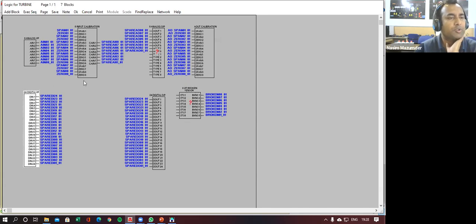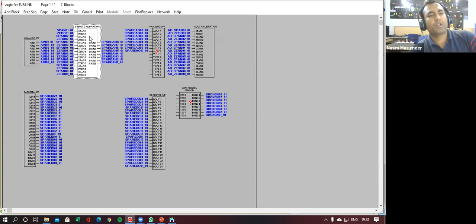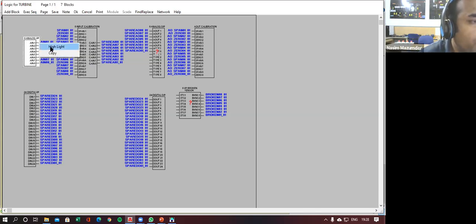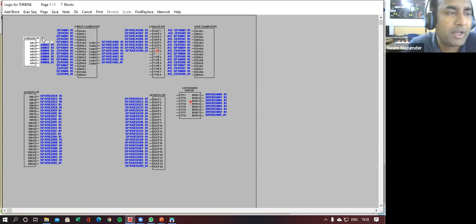The first block is written as 8 analog input, which means all the analog inputs are assigned here. The second block is written as 8 input calibration. That means channel number 1 here is analog input 0, 1. I can highlight it. At this pin, you can connect any analog input transmitter, any analog input field device.